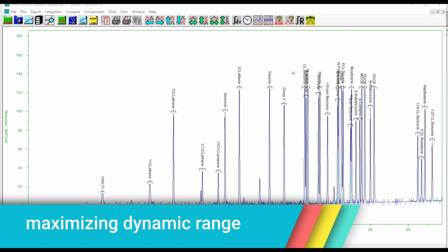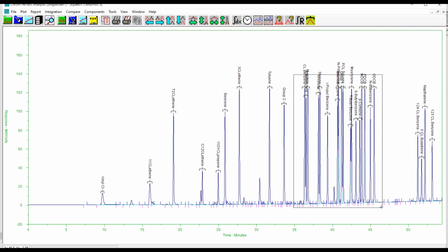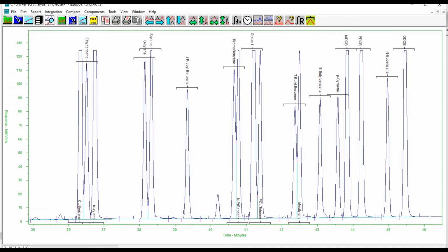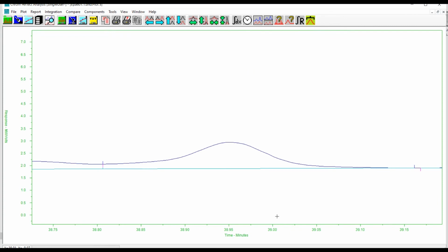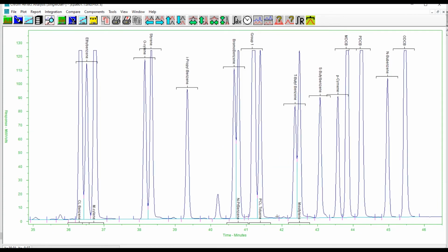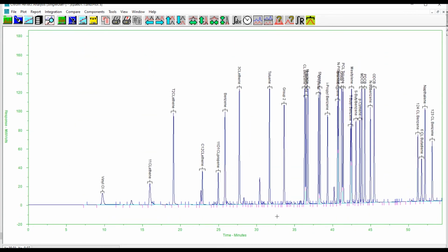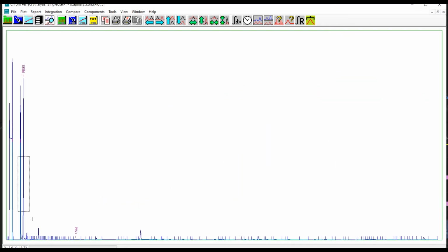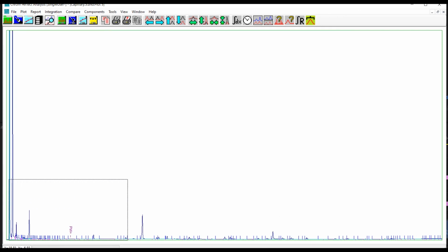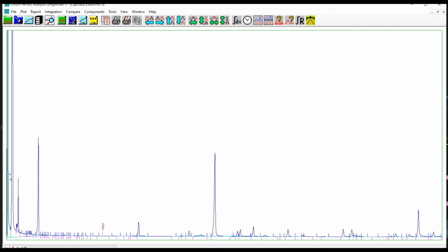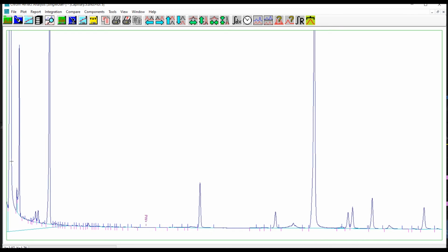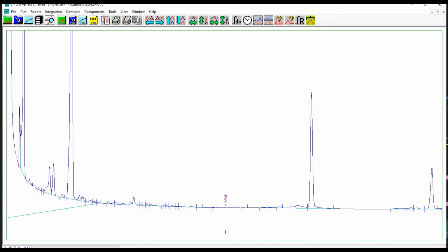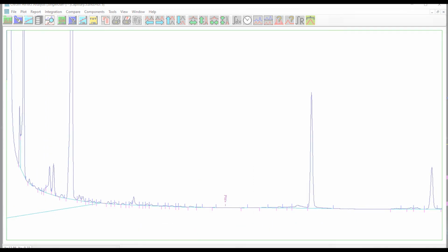Maximizing use of available dynamic range. Chromatography is distinguished from most other scientific measurements by the large dynamic range required. Many chromatograms contain both large and small peaks, and both need to be accurately quantified. Occasionally, a chromatogram will have small peaks on tails of huge solvent peaks. Therefore, the acquisition hardware must be able to record large signals without sacrificing the ability to see small variations.